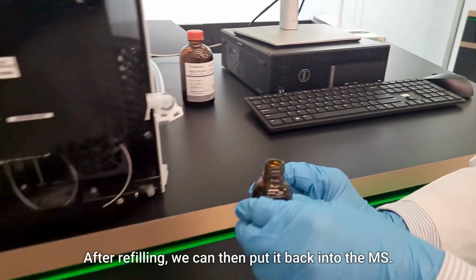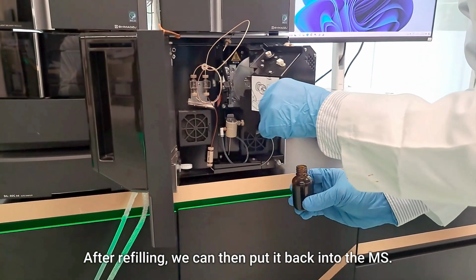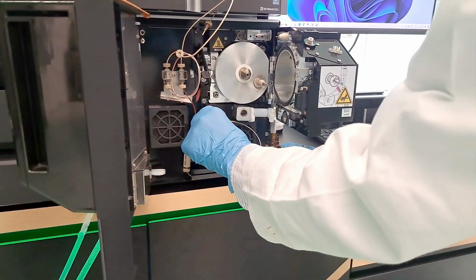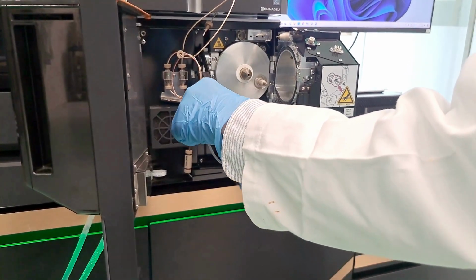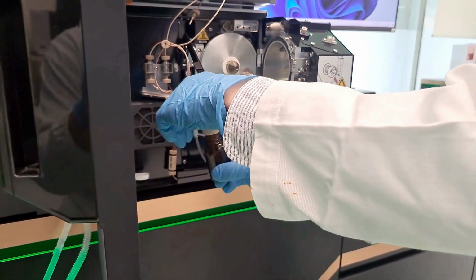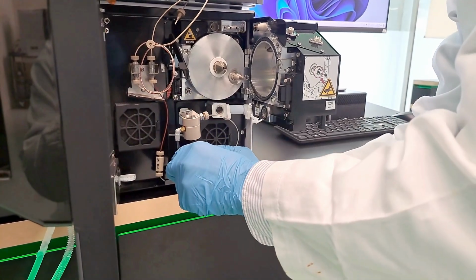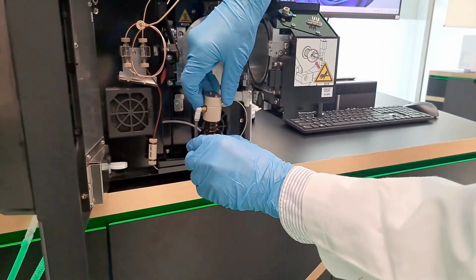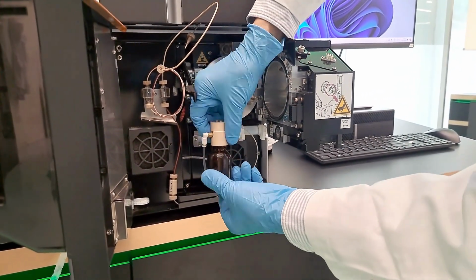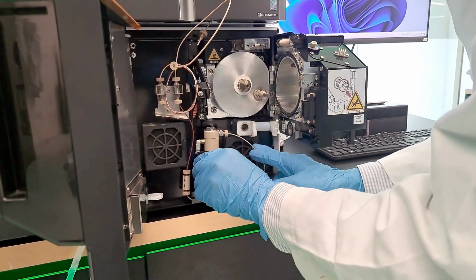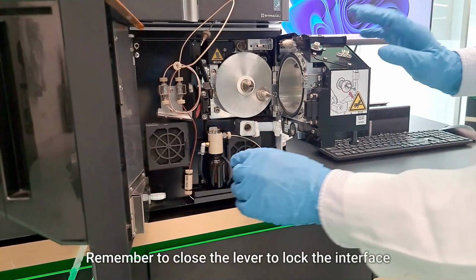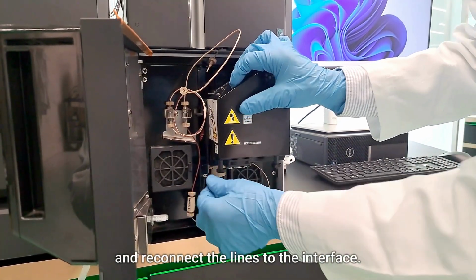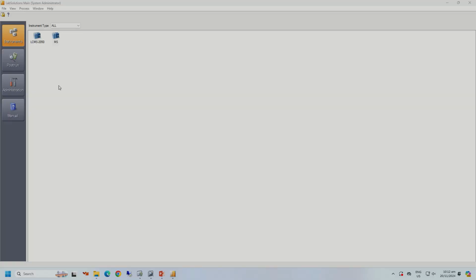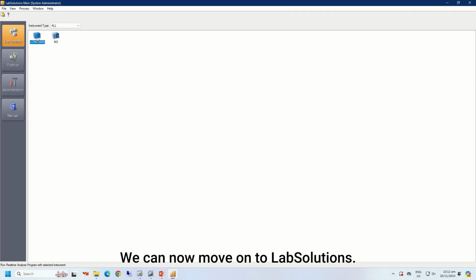After refilling, we can then put it back into the MS. Remember to close the lever to lock the interface, and reconnect the lines to the interface. We can now move on to LabSolutions.